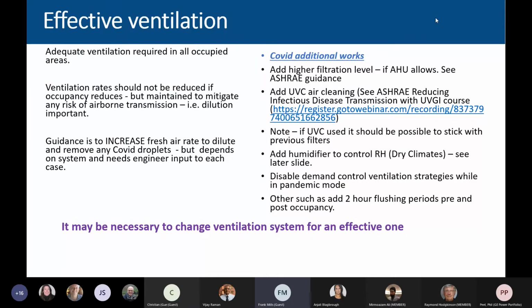There's quite a lot of additional advice there on the right-hand side of my slide, where you can look at filtration. Adding filtration is certainly one way of removing particles from the air, but we have to check with our design that the air handling plant we have, the air handling unit, has enough fan power to actually deal with a higher rate of filtration. So it may not be that easy.